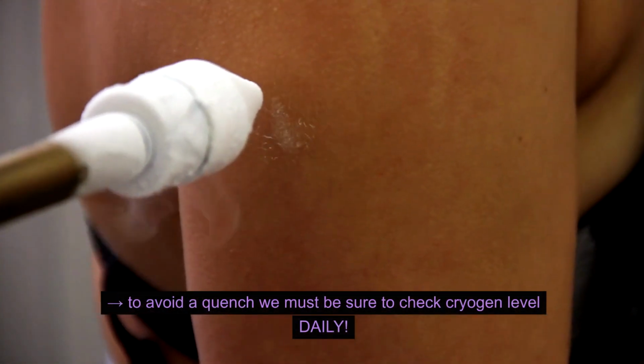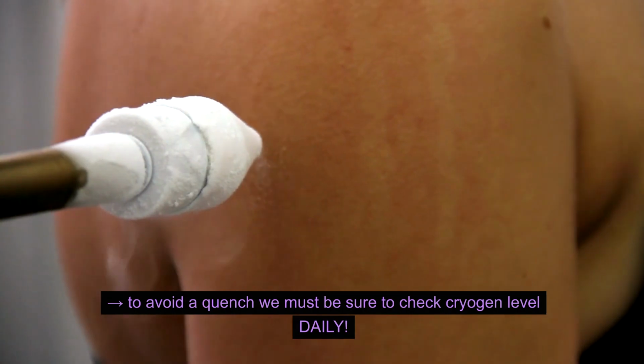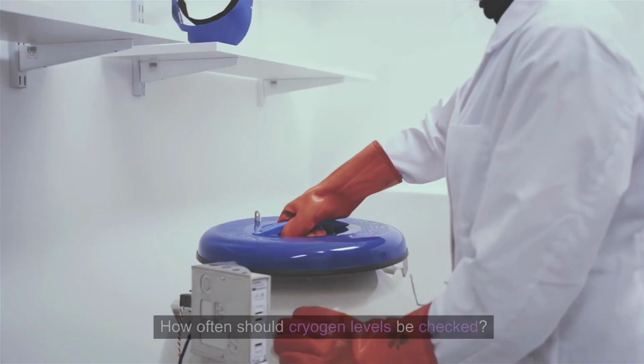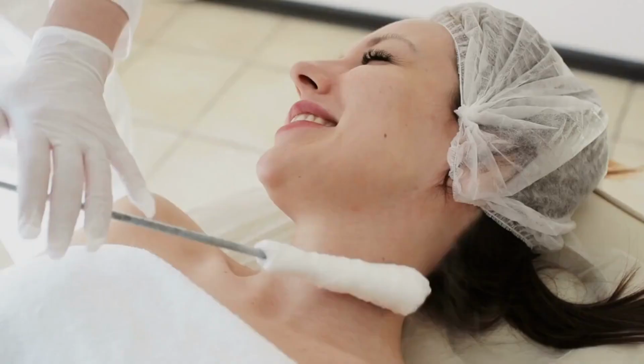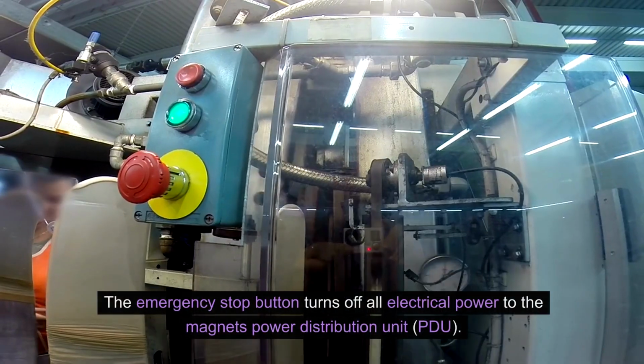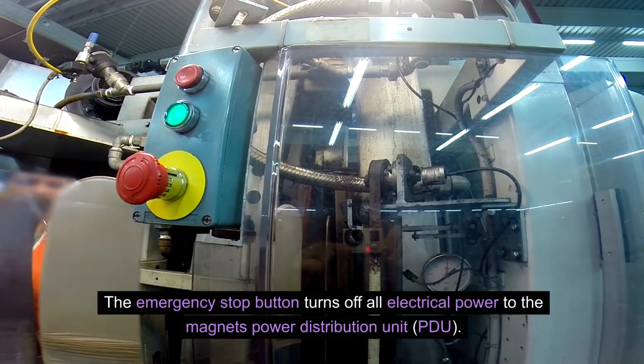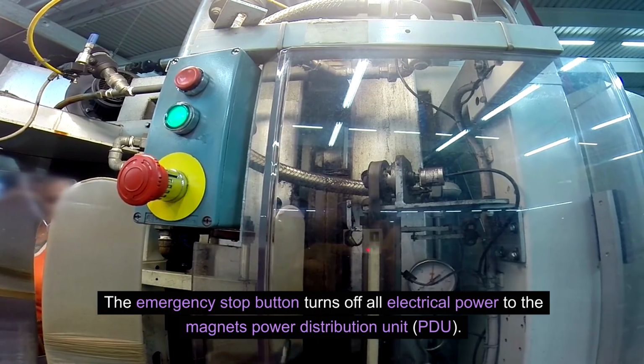To avoid a quench, we must be sure to check cryogen level daily. Question: how often should cryogen levels be checked? Answer: daily. The emergency stop button turns off all electrical power to the magnet's power distribution unit, PDU.